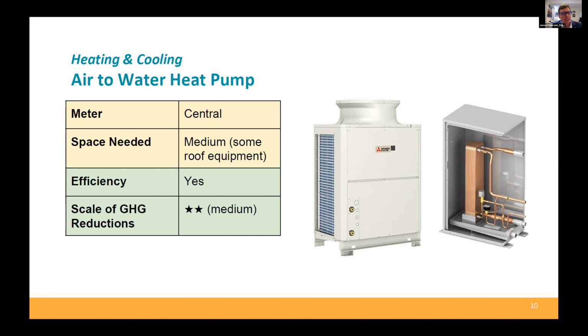The sorts of things you run into with existing buildings is you might have a building with high temperature perimeter hot water for heating, or a condenser water loop associated with a water source heat pump system. Often when a building is ready for capital improvement, there are issues with the existing hydronic distribution. You might get lucky, but we don't often see that compatibility due to the age of the prior system or its distribution. It might emanate from the basement, and now we want a system that starts at the roof. Just thinking off the top of my head. But generally we run into problems trying to mix and match new equipment with old systems. That's just a general difficulty.